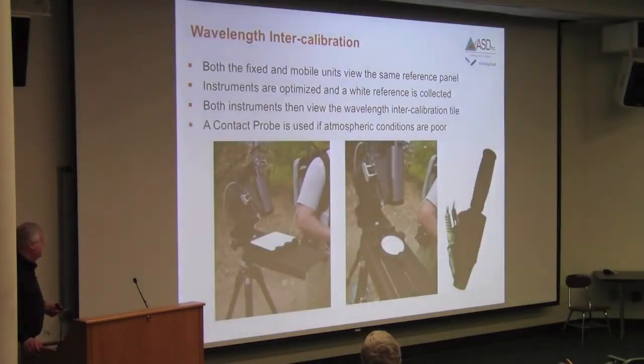So when you're out in the field, we built this fixture that allows you to mount the pistol grips holding the fiber optics of both instruments, so that both instruments are viewing roughly the same patch of real estate on the white reference panel. And the mount's designed so that these holders slide in, so depending whether you've got the round Spectralon or the 5x5 or the 10x10, they all fit on here.